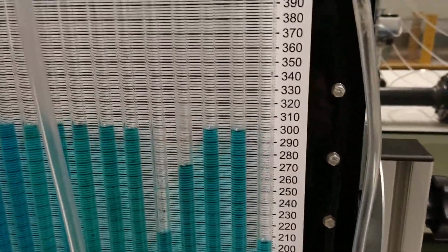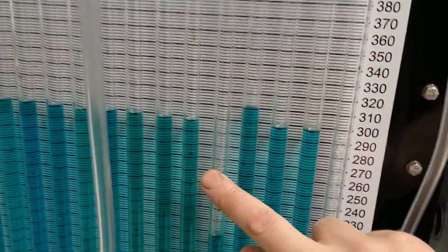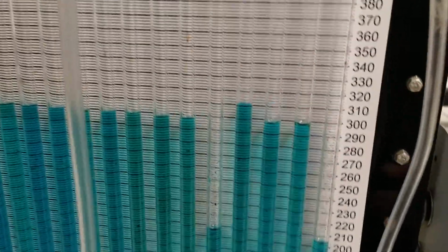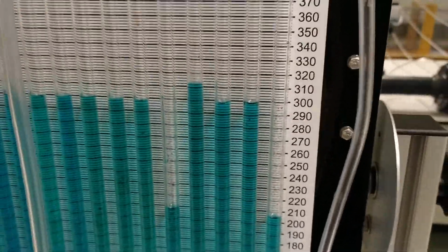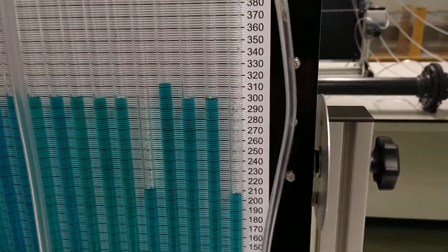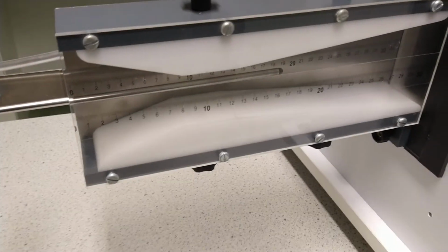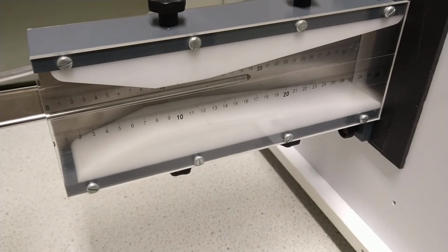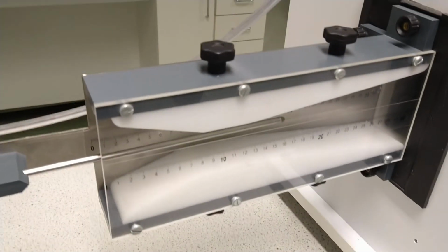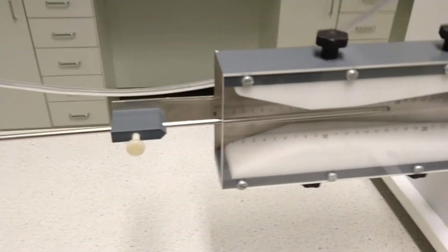Okay. Now what you can use that for is, if you look at the difference between the static pressure and the pitot pressure, that gives you the velocity pressure. If you have the velocity pressure, you can work out the velocity from that. So a pitot-static tube can be used to measure pressures, but it can also be used to measure velocities. So you sometimes see pitot-static tubes, let's say on the front of an airplane, to measure relative airspeed. Okay, and you can hook those up to a manometer, or you can also hook them up to an electronic pressure gauge.